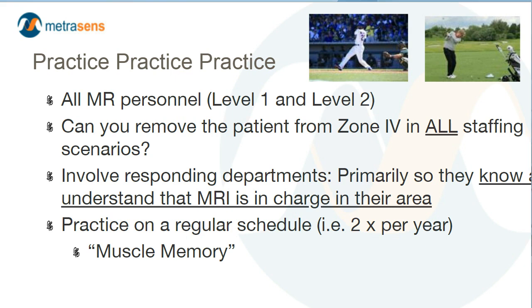It's important that non-MR personnel understand that MRI personnel are the ones in charge of their area. Mock codes should be practiced on a regular schedule. Our recommendation to our clients is two times per year. Like athletes, the more familiar MR personnel are with the procedure, the more it becomes like muscle memory.